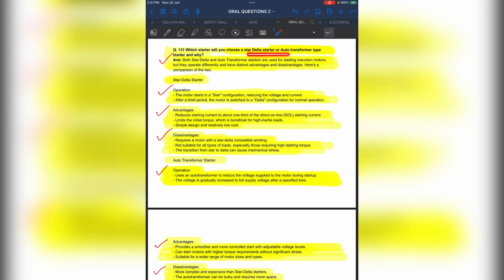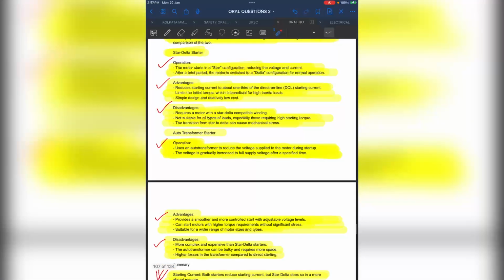Which starter will you choose, a star delta starter or an auto transformer type starter? Why? So, a surveyor will ask which starter you will choose, star delta or auto transformer. If you choose star delta or auto transformer, why, and what are the reasons for choosing that starter? So, let us discuss the star delta and auto transformer starter. In a star delta starter, basically the motor starts in a star configuration. First the motor starts in star configuration, which means the voltage is reduced at that time, and we give reduced voltage and reduced current to start the motor, and after that we switch over to delta, giving the normal full voltage supply to run the motor.